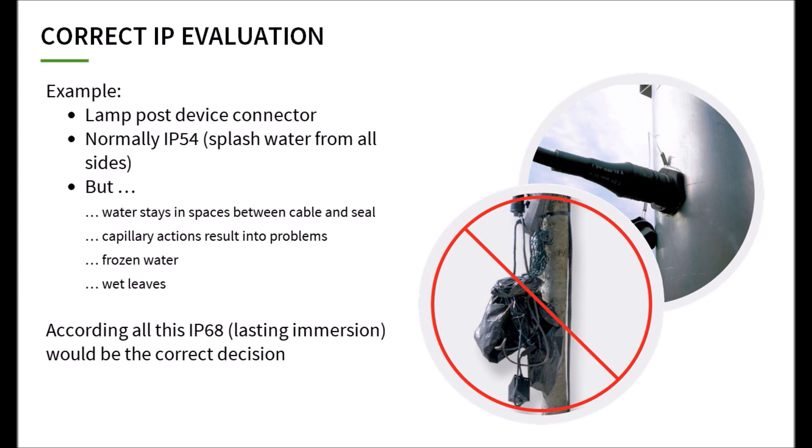This effect is further enhanced by vertical installation of the plug connector or device connection. Water is repeatedly fed through the pipe to the sealing area, which is often submerged for weeks during rainy periods. Without measures to avoid this situation, protection class IP68 must be used accordingly. The penetrated water also freezes in winter and contributes to accelerated aging.